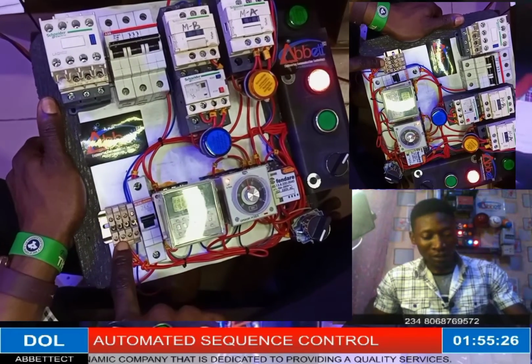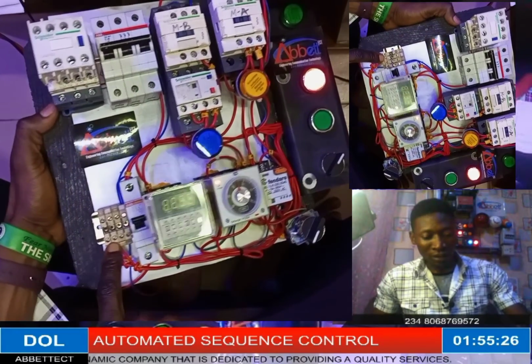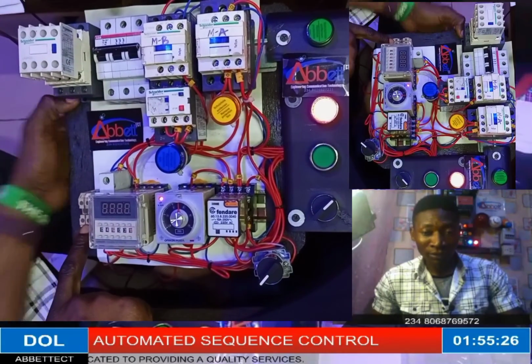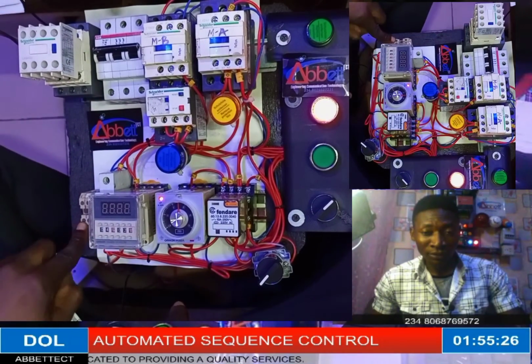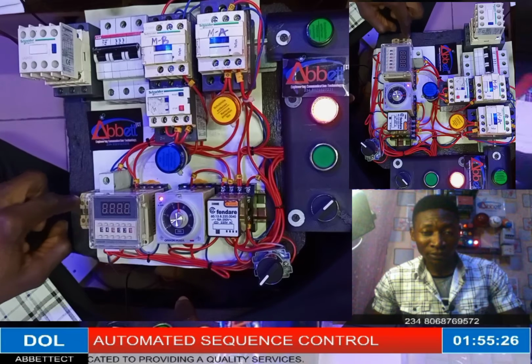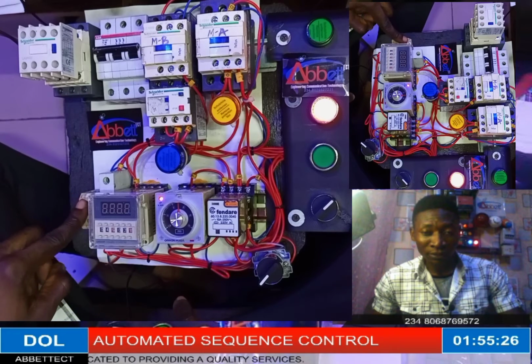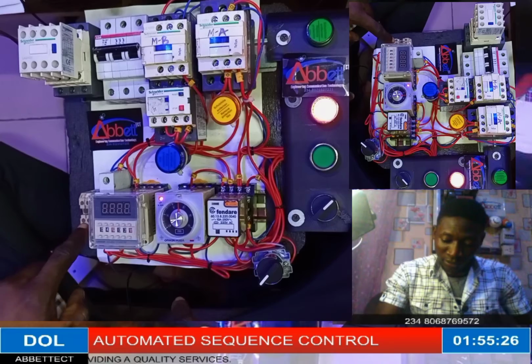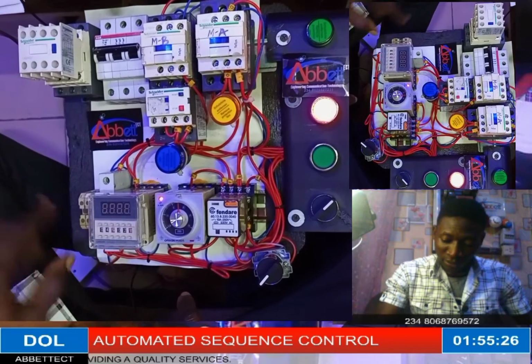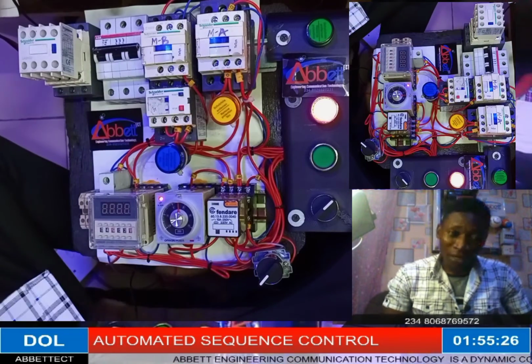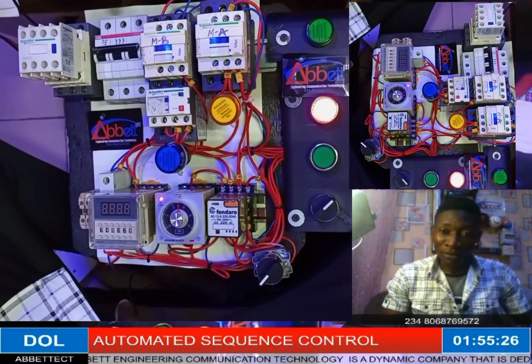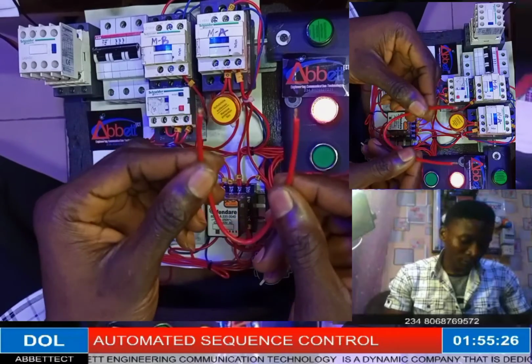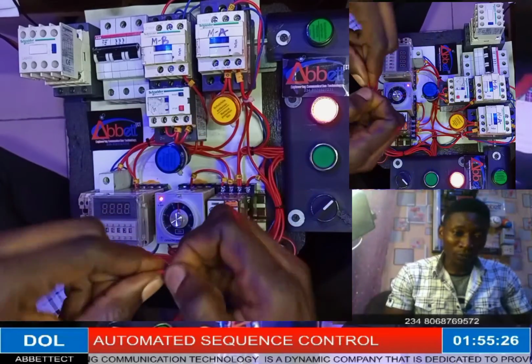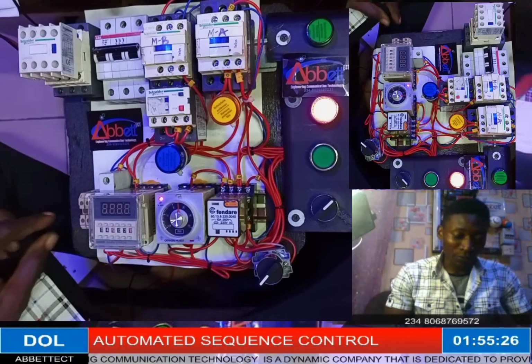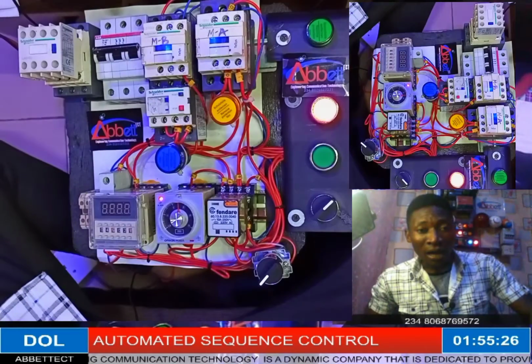These two terminals are where you connect the signal that is coming from the machine in the field. This is where you are going to terminate it. We have some terminals here, and the labels are there. These are the two major ones you're going to be using. They dictate to the system when to operate and when not to operate. Because there's no signal coming, I'm just going to use this loop to serve as the signal. So immediately I close these two terminals, it will still operate normally.